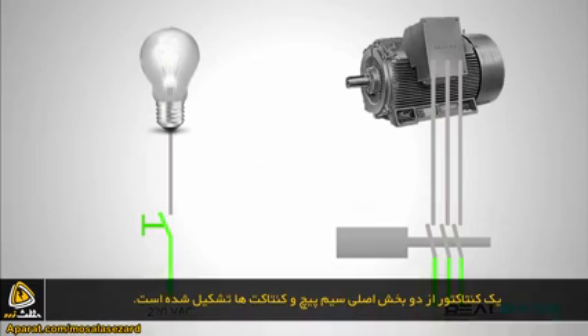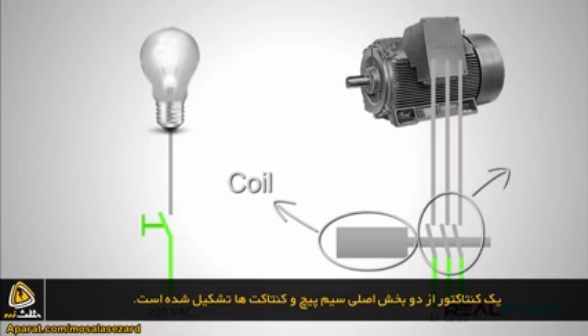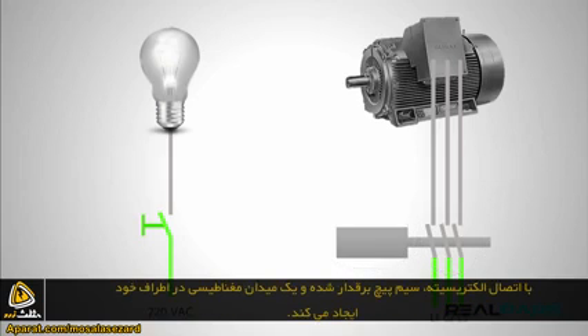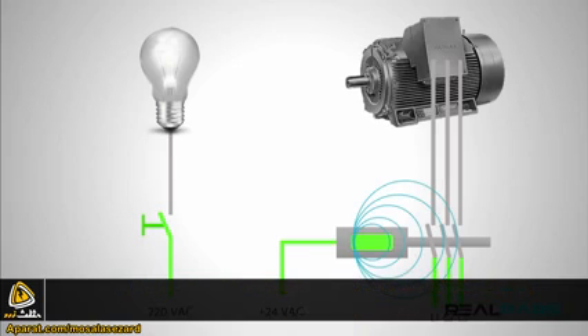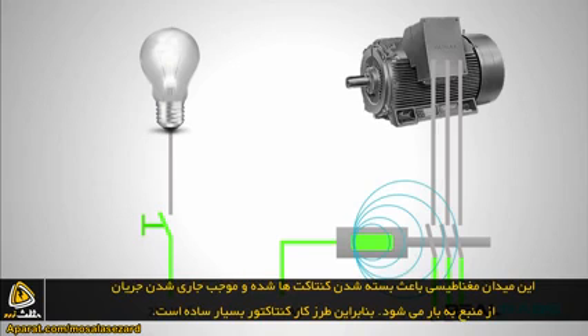A contactor is composed of two main parts: coil, or electromagnet, and contacts. When you connect power, or electricity, to this coil, the coil is energized and creates an electromagnetic field around itself. This field causes the contacts to close, which allows the current to flow from source to load.